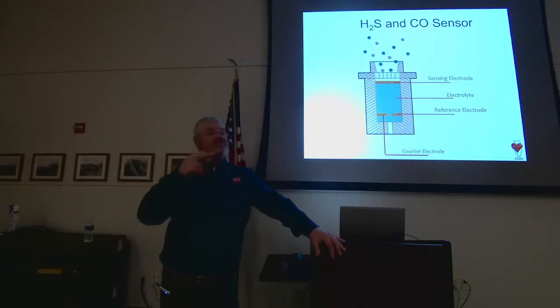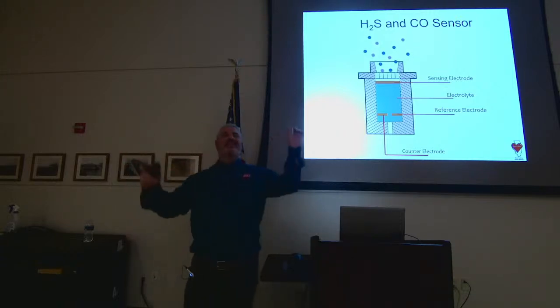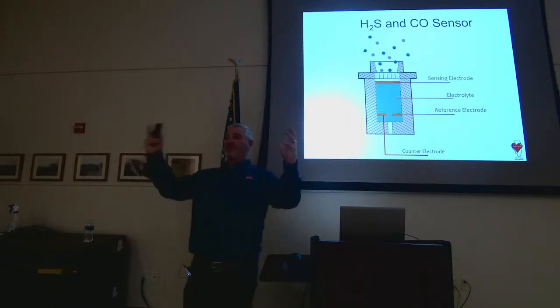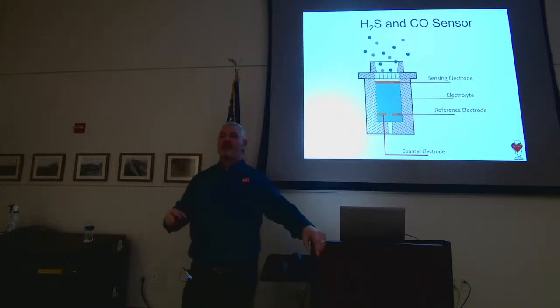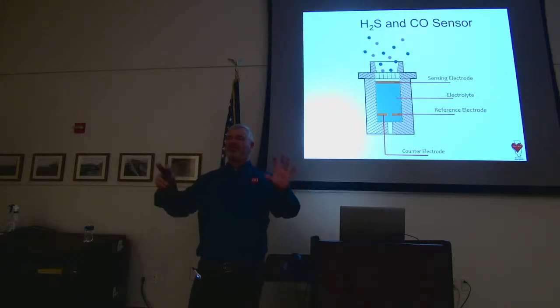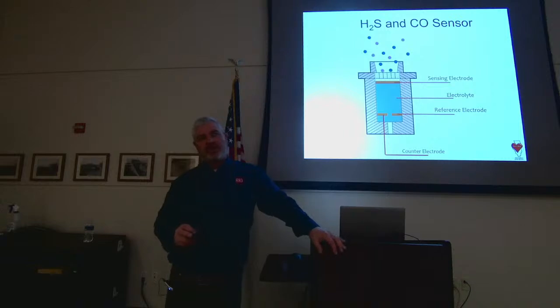Now the H2S and CO sensors are totally different. This is a little bit misleading, it makes it look like they're one, but the two sensor technologies have two different electrolytes in them, so they won't respond to each other, but we do put some filtration in place. So with that said, my H2S and my CO sensor is going to last longer than the O2 sensor, because the O2 sensor works all day long, every day, 24/7.